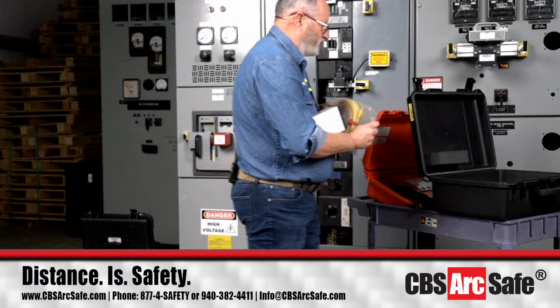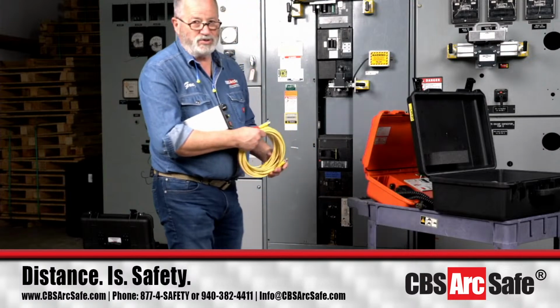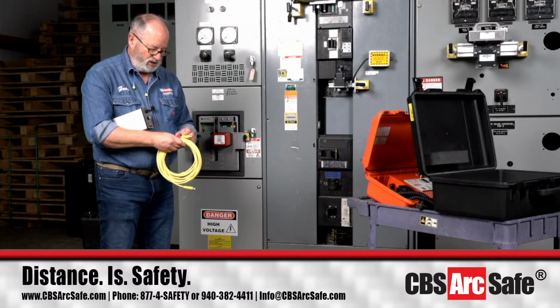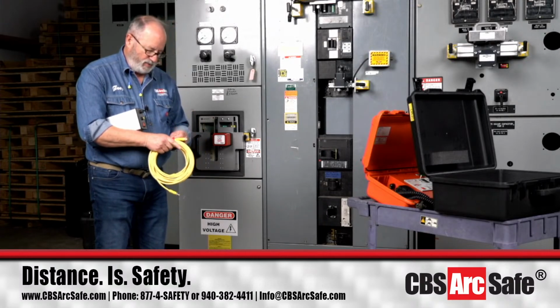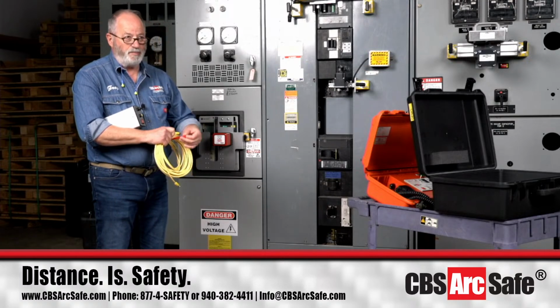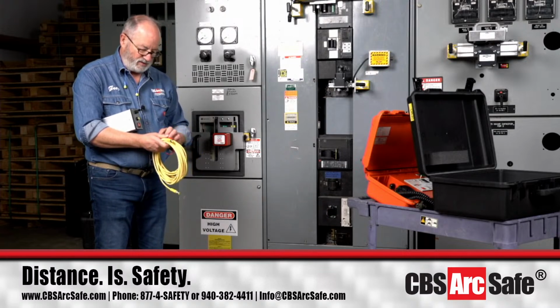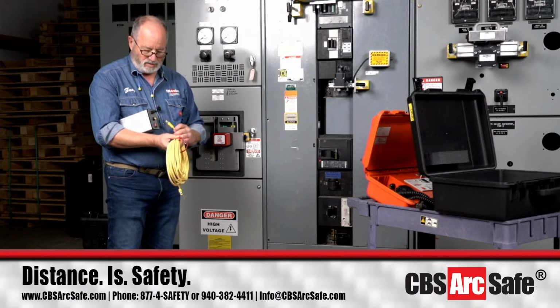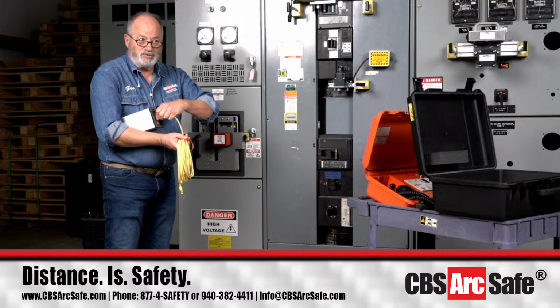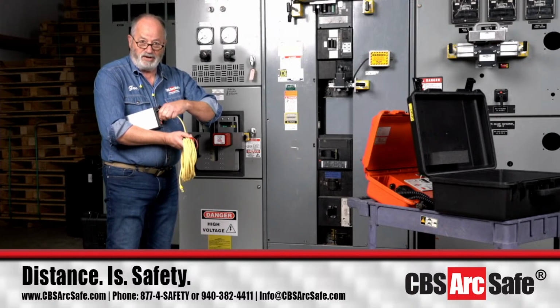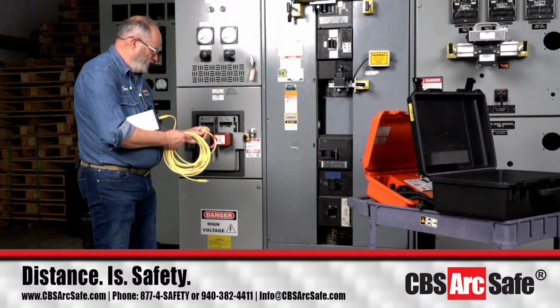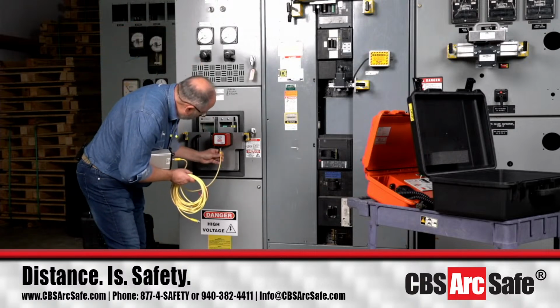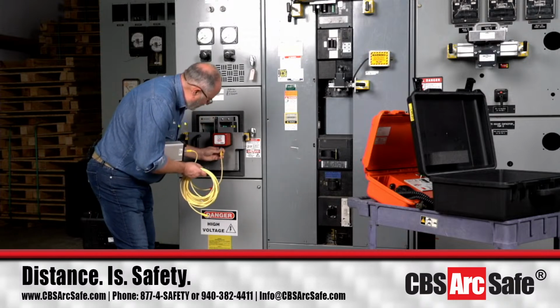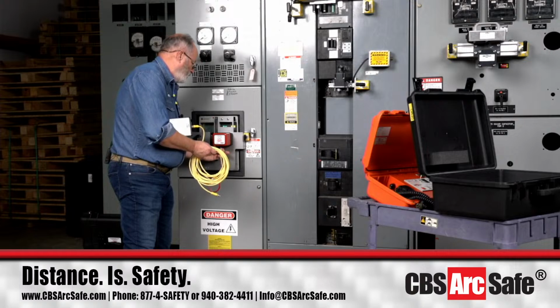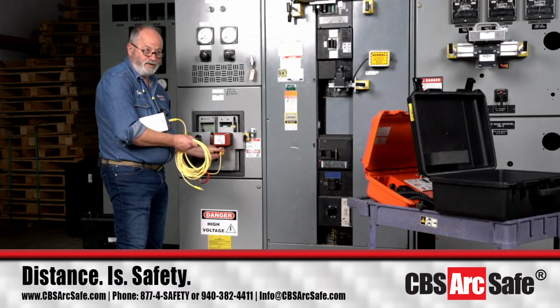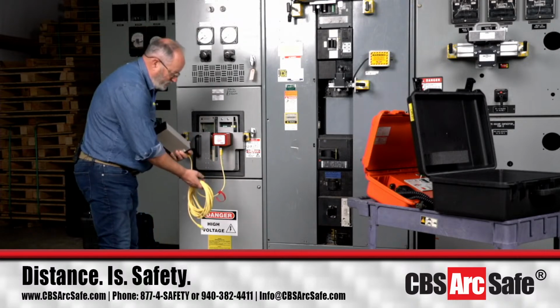Most data centers today, unlike old ones, which usually only had 3,000 amp mains with K-line or GE AK breakers, are different. Today's facilities, whether a bank, an internet company, or a government facility, tend to have 5,000 amp up to 6,300 amp mains as the main incomers on low voltage. That's what drives higher incident energy, since you have so much amperage to move around for all the servers in a limited footprint, without enough area to dissipate arc fault energy. If you build a data center in Colorado, for example, you're putting it on rock, so you don't have many places to get rid of that energy.